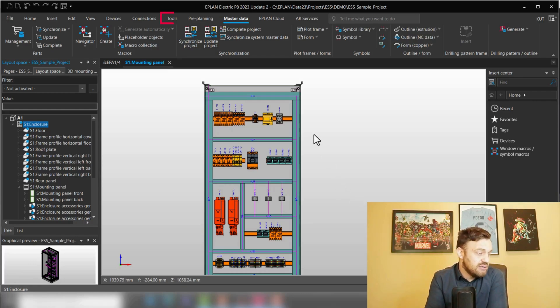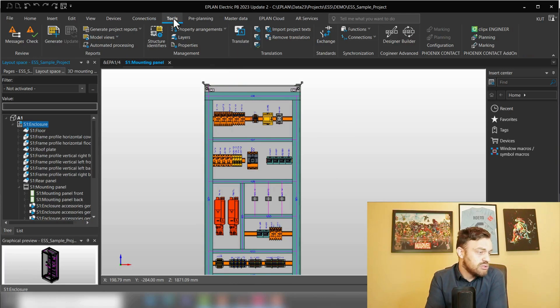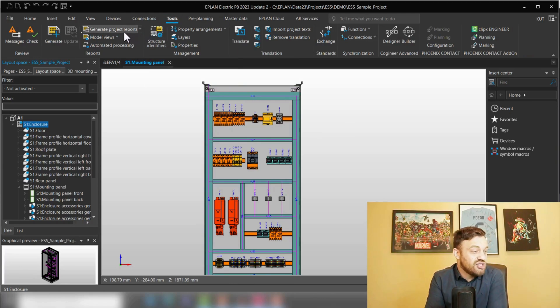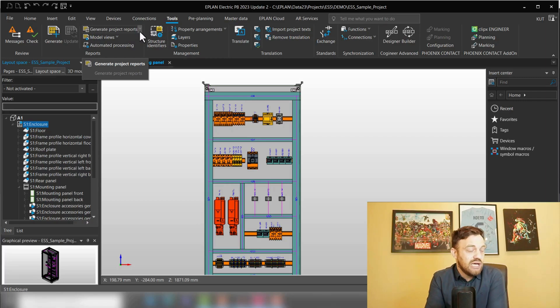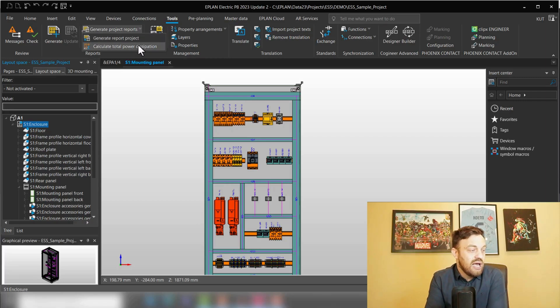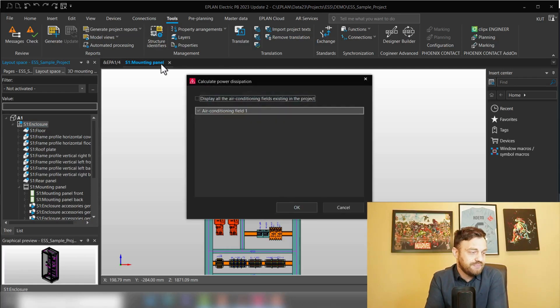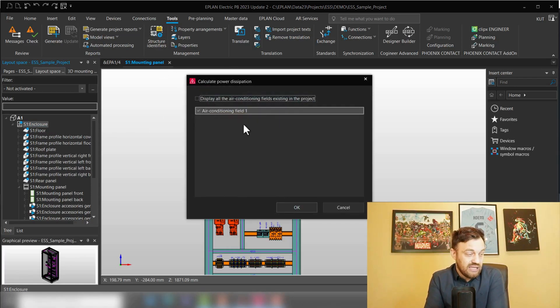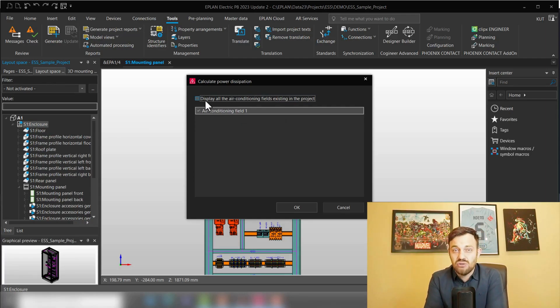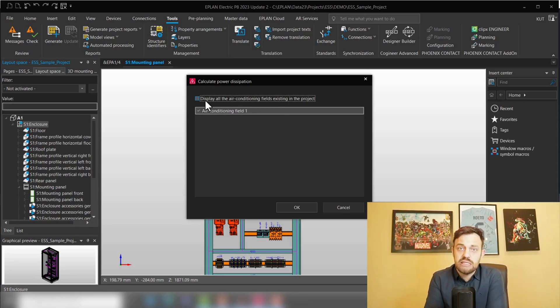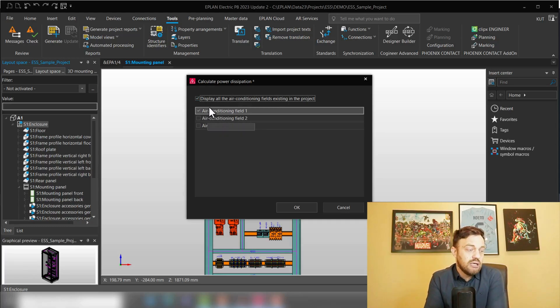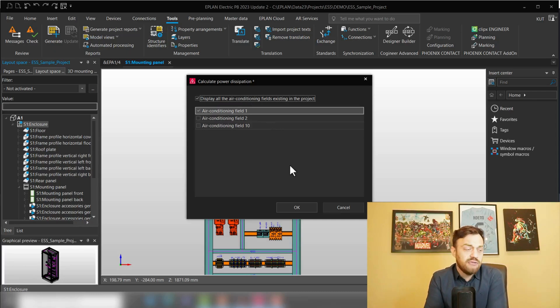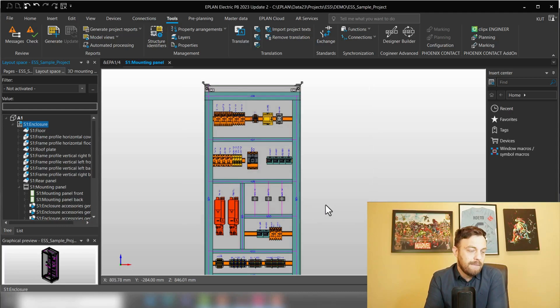For this, we will go to Tools and here under Generate Project Reports we can press the arrow down and select Calculate Total Power Dissipation. EPLAN knows that I'm in this enclosure, so it says air conditioning field one. If I would like to calculate for multiple air conditioning fields at the same time, you could select here display all the air conditioning fields and then you can activate those. In our case, air conditioning field one is the only one we need and we will press OK.